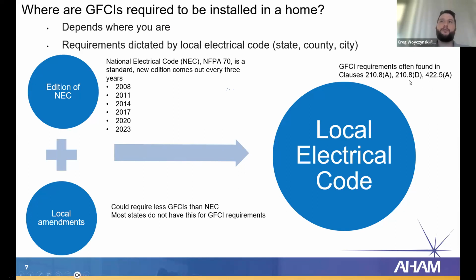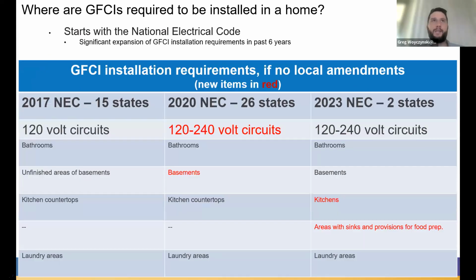And there are 3 paragraphs in electrical codes that lay out the requirements for where a GFCI is required: 210.8(A), 210.8(D), and 422.5(A). So these are available for free online, whether it's the National Electrical Code or your local electrical code. And these are written in layman's terms. You don't have to be an electrician or an electrical engineer to understand these. These are the numbers you want to look for in your local electrical code or the National Electrical Code when you're trying to find the GFCI requirements. A little more detail on where a GFCI is required to be installed in a home.